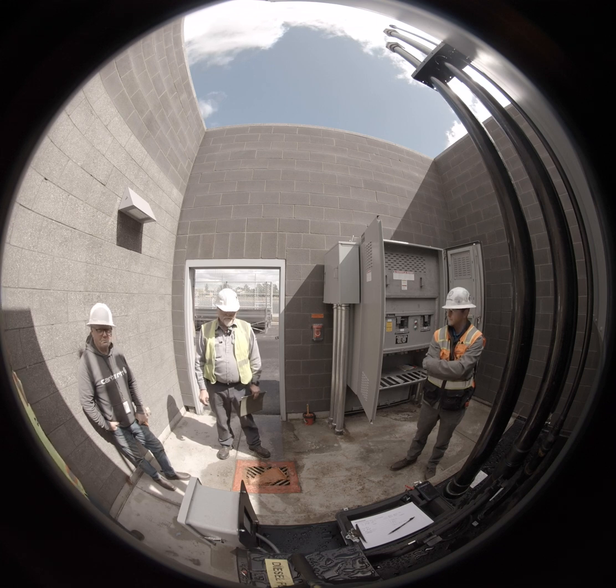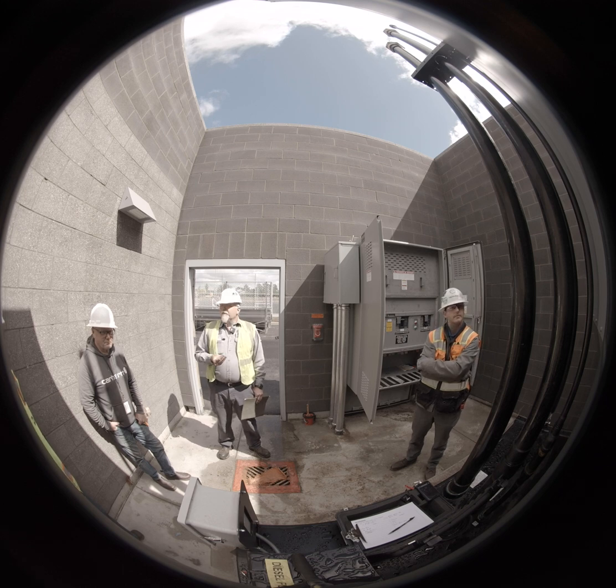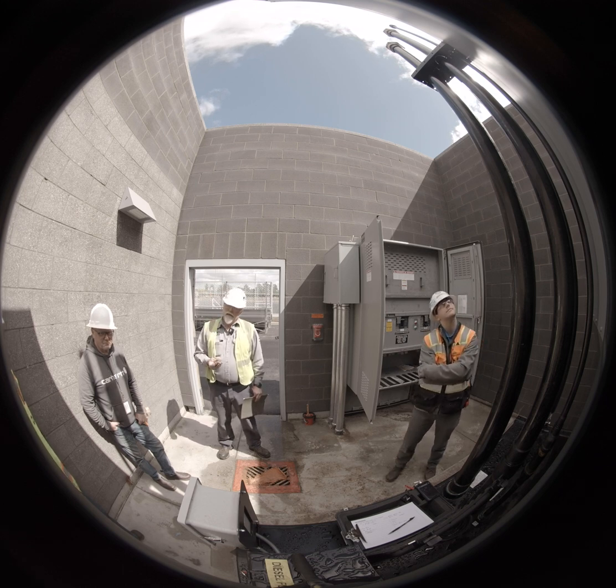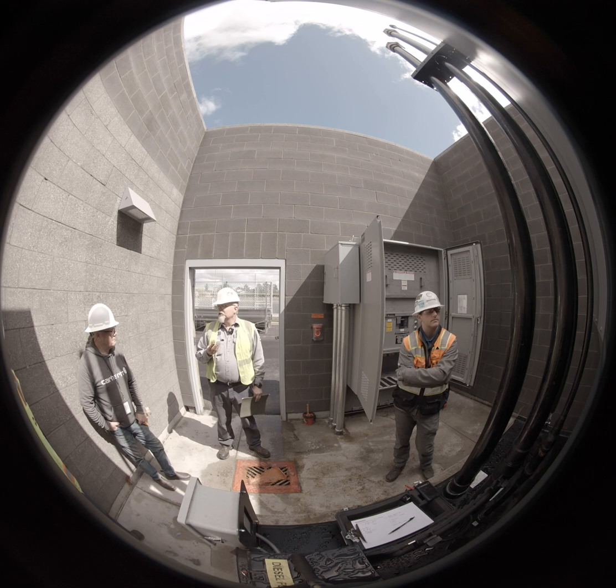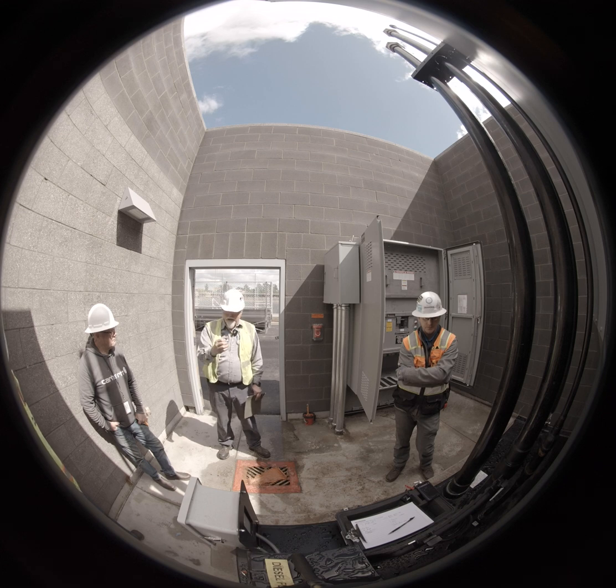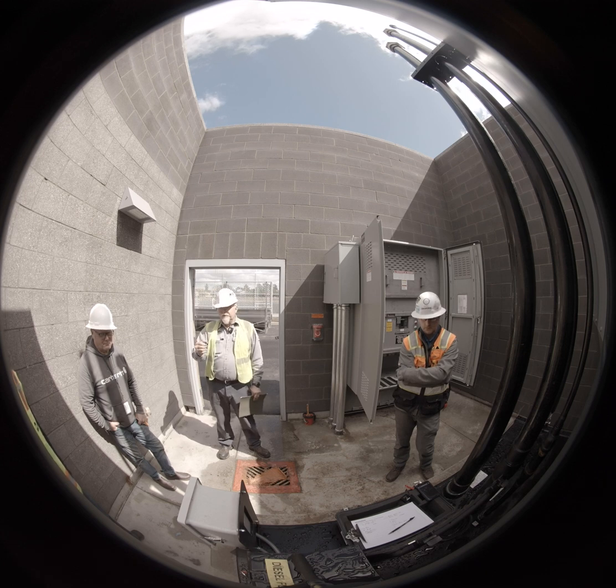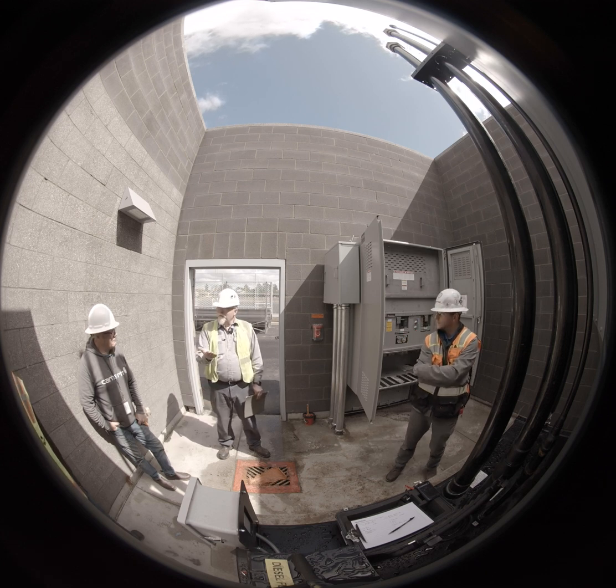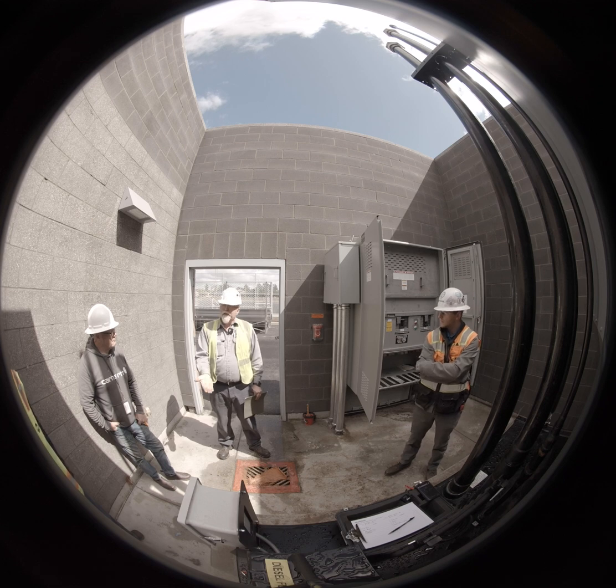So the fueling of this tank goes in through a swing arm overfuel prevention valve. When the truck company comes in, they will cam lock onto this tank. You have to use a cam lock with this specific style. They cam lock on, they will push fuel in, and the fuel level will come up, and if they put too much fuel in, it will close off and basically shut down their pump.